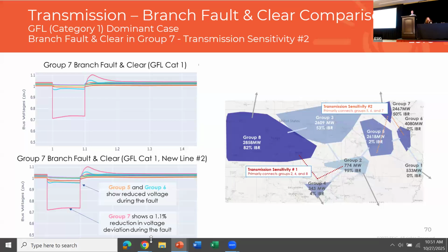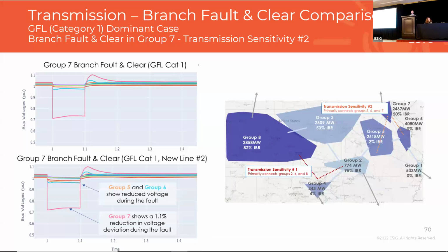From a voltage standpoint, we've also looked at it the same way, and again we see a similar phenomenon. Looking at voltage within the fault, groups 5 and 6 show reduced voltage during the fault, and group 7 shows a reduction in voltage deviation—an increased voltage during the fault—in the sense that the voltage support, or reactive power, is flowing from groups 5 and 6 to support group 7, where the contingency actually occurred.